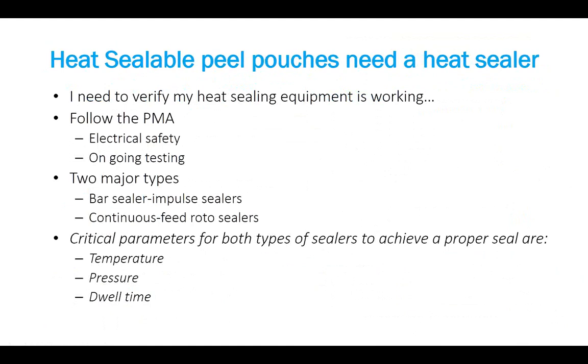So heat sealable pouches need a heat sealer. You need to verify the heat sealing equipment is working. One, you follow the PMA, and that's usually by your biomed. Electrical safety and other things, is it putting the right output? Does it have a UL or CE on it? What are the different parameters that they must check?